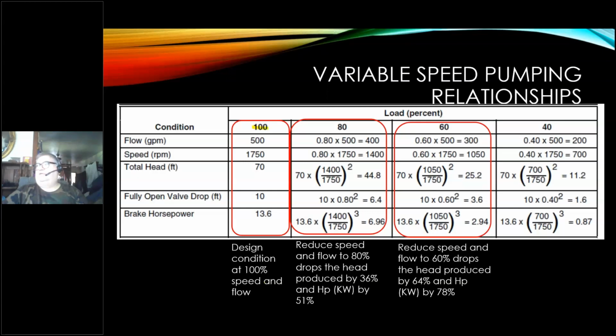It's amazing. Typically, systems will operate between the 80 and 60% section. They rarely get up to 100%, unless you're at the very extremes of the design, and that's only maybe 10% of the time, really. The design is there to maintain operation at 100% of your heat transfer, and the only times that you should see that is on those days that you have 100% load. That's rare. So we actually operate at 80 to 60%.